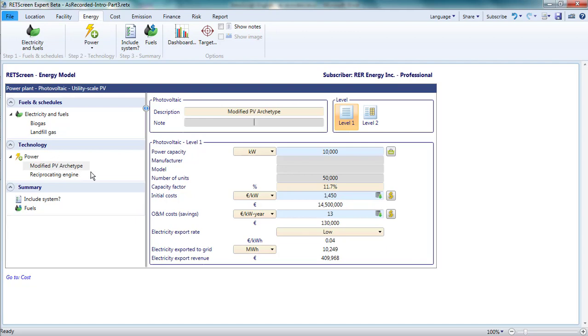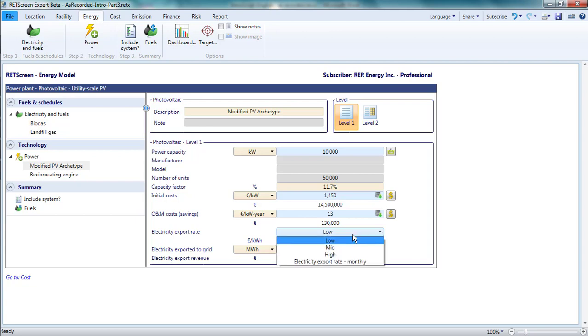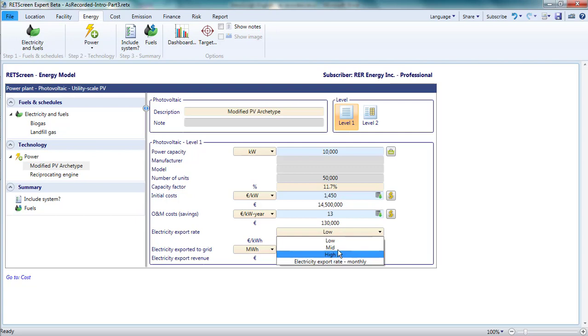Second, the key outputs for the analysis are the annual electricity exported to the grid and the annual electricity export revenue. The word annual does not appear in the RETScreen parameter descriptions, so don't forget that these are annual values. In RETScreen, export means electricity production that is sold to the grid at the electricity export rate. The electricity export rate is selected from a drop-down list which includes all the tariffs previously specified under the electricity and fuel section. I'll pick the mid-export tariff of 5 euro cents per kilowatt hour.